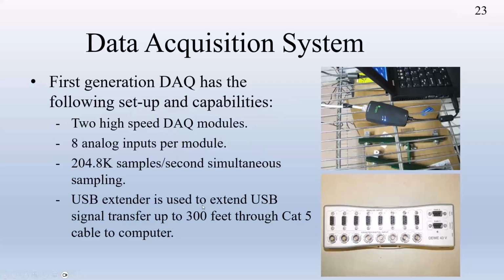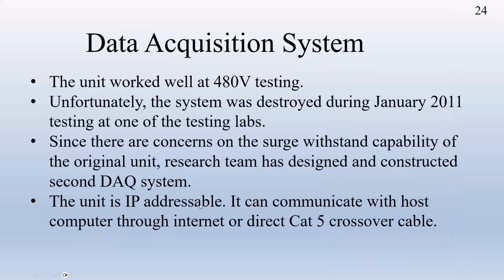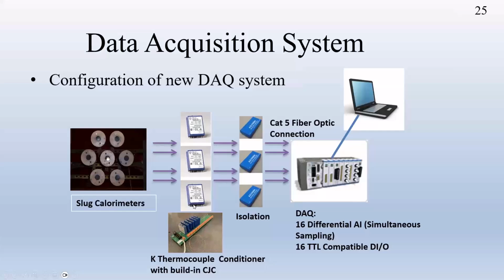So during the second test, it was out. I went back and came up with my own design. Here is the calorimeter, and then you have a thermocouple going through a conditioner that converts to voltage, then through the isolation here, and into the CompactRIO, and then we use an optical fiber connection between the unit and the computer. In that way we are able to create isolation, for the sake of the equipment and for the sake of the person.